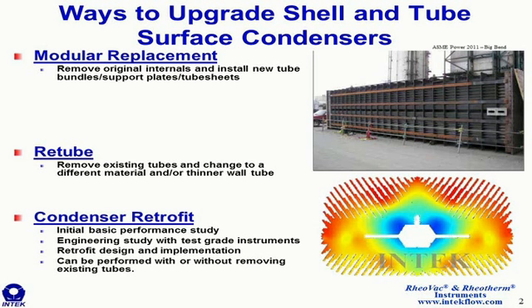The construction can be performed with or without a retube. It's completed in a short outage length and very little risk to the plant in terms of impacting the outage schedule. The process for a condenser retrofit typically starts with a two-step engineering study. So I want to talk about the condenser retrofit process, which starts with understanding condenser performance.